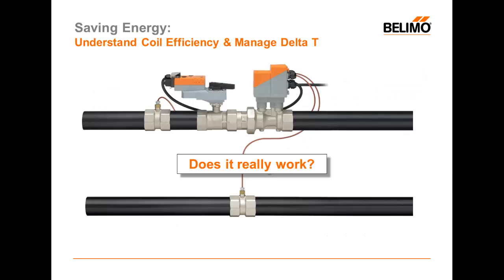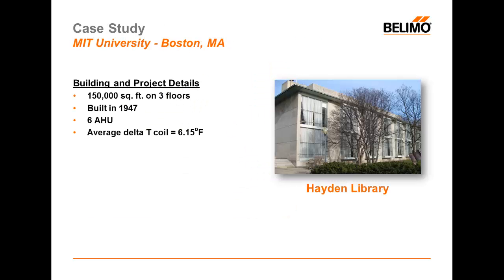Let's take a look at some real-world examples where the energy valve has been installed and Delta-T management has been very successful. We'll start with our first case study at MIT University in Boston. At the Hayden Library on the MIT campus, all of the air handler units were retrofit with the Belimo energy valve. The Hayden Library is a 150,000 square foot building over three floors, built in the late 1940s. Six air handlers were retrofitted, and previous to Delta-T management, the measured Delta-T of those coils was just above 6°F.